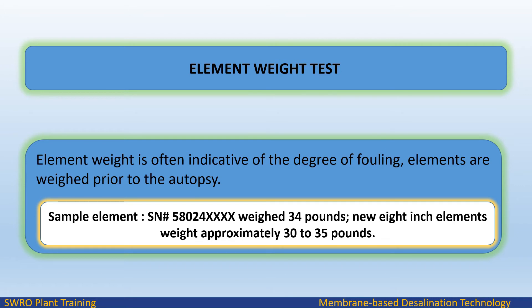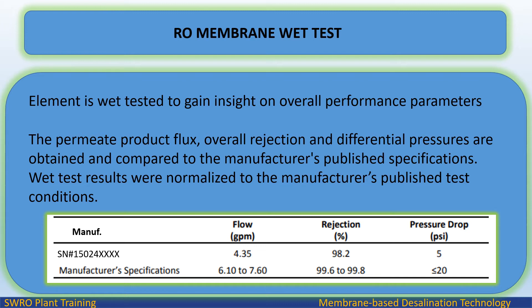Element weight test: Element weight is often indicative of the degree of fouling. Elements are weighed prior to the autopsy — a sample element weighed 34 pounds, while new 8-inch elements weigh approximately 30 to 35 pounds. RO membrane wet test: The element is wet tested to gain insight on overall performance parameters. The permeate product flux, overall rejection, and differential pressures are obtained and compared to the manufacturer's published specifications, with test results normalized to those conditions.